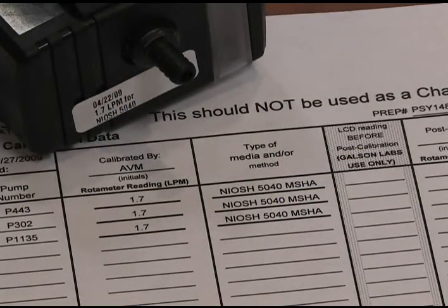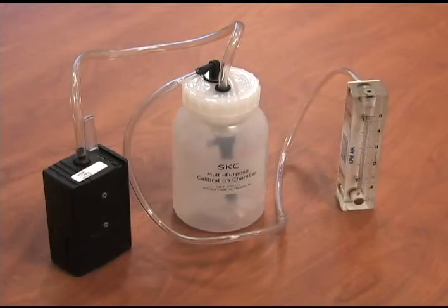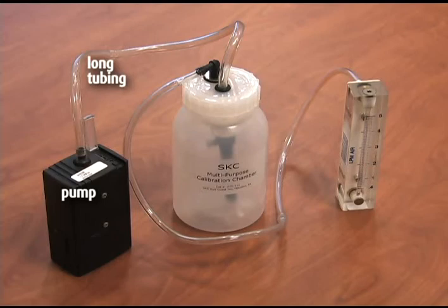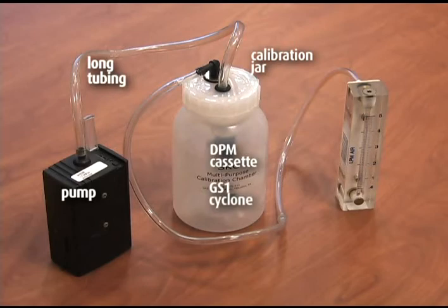All pumps have the lab calibration information on the pump calibration data sheets provided. Set up the pump with the correct media in line, with the field rotometer as shown. The order of the components for calibration is pump, long piece of tubing to jar inlet, calibration jar, DPM cassette, GS1 cyclone, long pieces of tubing from the jar outlet, and rotometer.